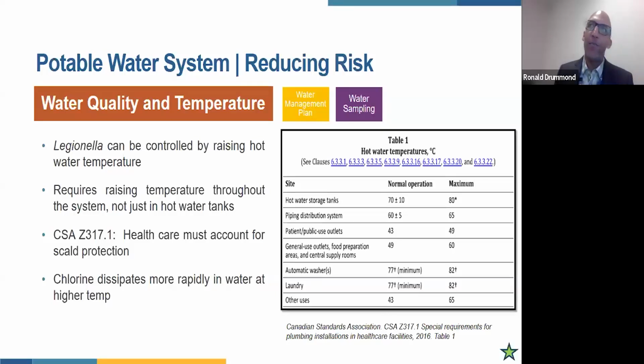The other point that I like to raise when we talk about Legionella and chlorination and the amount of chlorine in the water is that the higher you keep your loop temperature, the faster the chlorine is going to dissipate within the water. So just be wary that the higher that you keep that temperature, you might be consuming more chlorine. You might be injecting more chlorine than you have to achieve that higher water temperature.